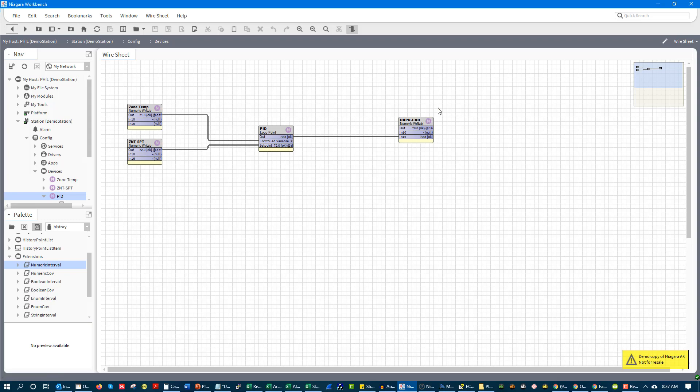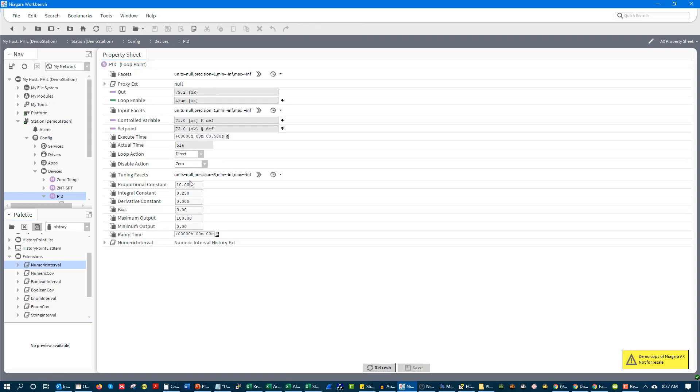And then our actual range, our throttle range, is 0 to 100 for our output because we have a 0 to 100% command. So when those two numbers come together, typically it's throttle range divided by sensor span. That gives us our proportional value.